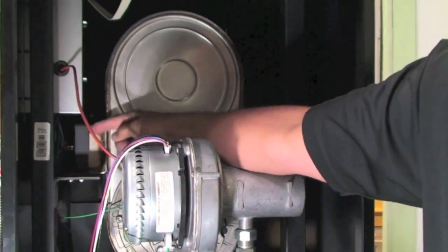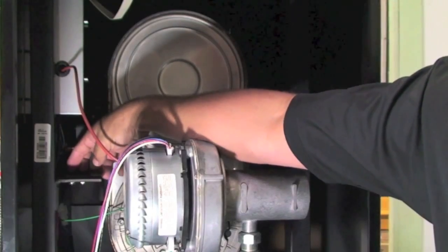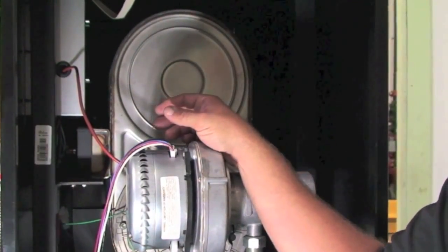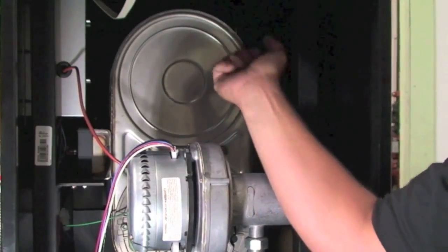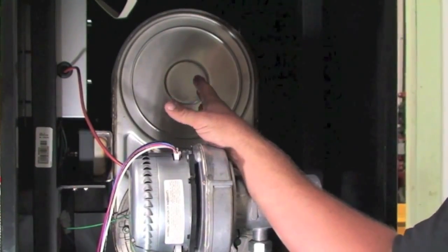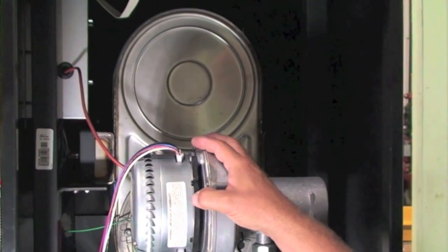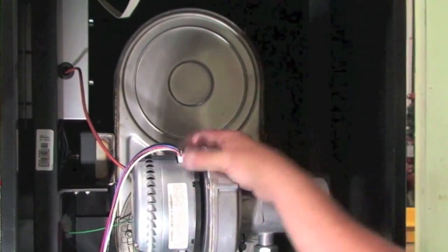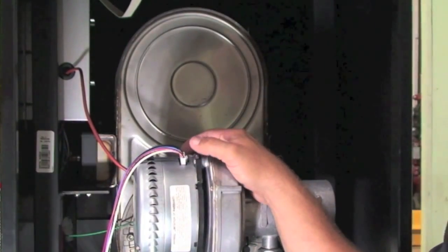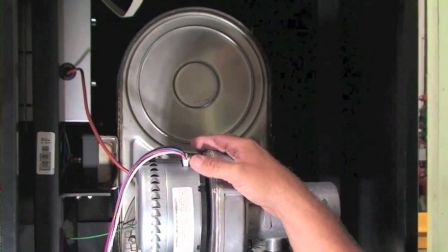We have lock-in brackets that can be taken out very easily and you can slide the whole heat exchanger out. We have little clips on the return and supply so if you ever have to replace a module or heat exchanger, it's easy to do. That's both on the bottom and the top unit. If you have a problem with one of the units long term, 20 years down the road, you can go ahead and service the top boiler and keep the bottom boiler running while you're doing your service work. Again, that's the importance of the redundancy.